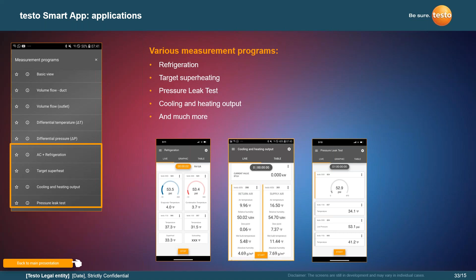Then you take the manufacturer's data from their service facts or installation manual, wherever they decide to put it, and take the outdoor dry bulb, indoor wet bulb, and run through that system to see what the manufacturer says it's supposed to be doing in that same situation. It will show you how accurate and how close it is. And if something's missing and it's not doing what the manufacturer's specs say it should be doing, then you know you've got other things going on there. So, great tool, great application.